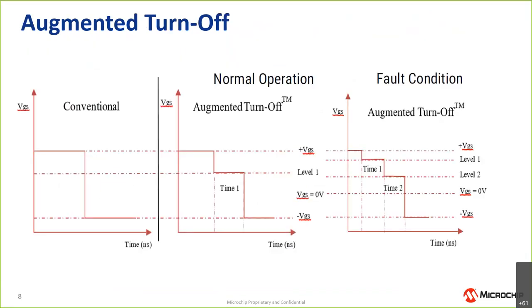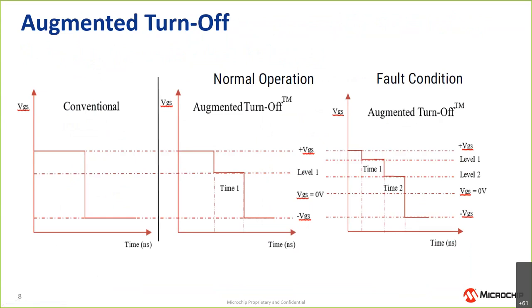In a conventional two-level turn off, you tend to have either some fairly fixed values or perhaps a few choices, but overall fairly fixed. With augmented switching, we've introduced additional levels and the ability to control the voltage level and the time at that level quite precisely. We've got an approach for both normal operation where you're typically looking to maximize efficiency and minimize overshoot, versus short circuit operation where we've introduced an additional step because the goal there is not so much to worry about efficiency but to safely shut down the device.